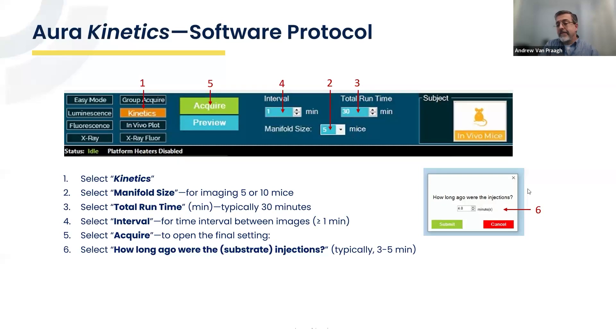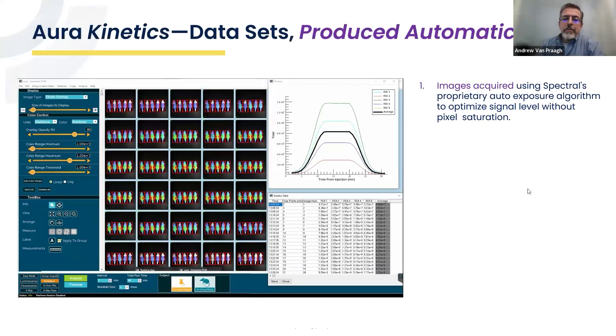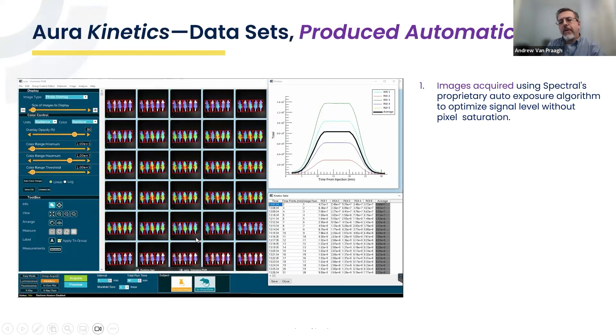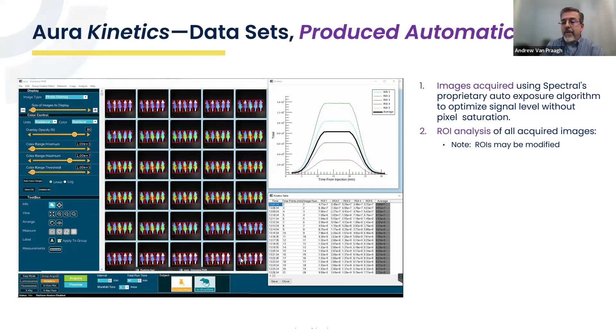The time of injection onset is a very key parameter to enter correctly — you'll need to be consistent on that front to have meaning across your various kinetic curve evaluations. Typically we use the time of onset of first dosing and the time elapsed before clicking Submit, which will launch the kinetic software. You can alter the whole-mouse ROI default during acquisition to focus on the brain, liver, or heart, specifically getting a region of interest analysis for those sub-regions of the overall mouse anatomy.